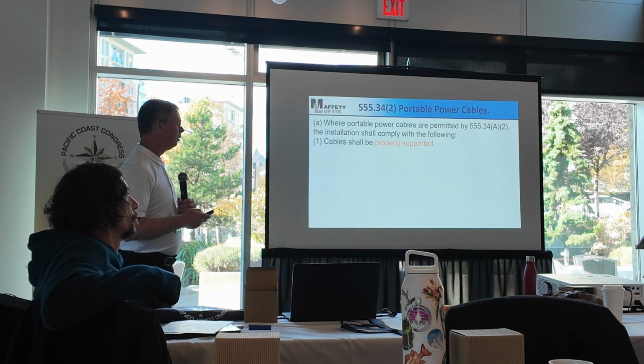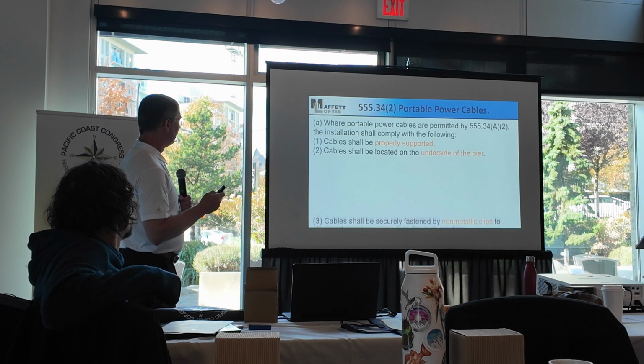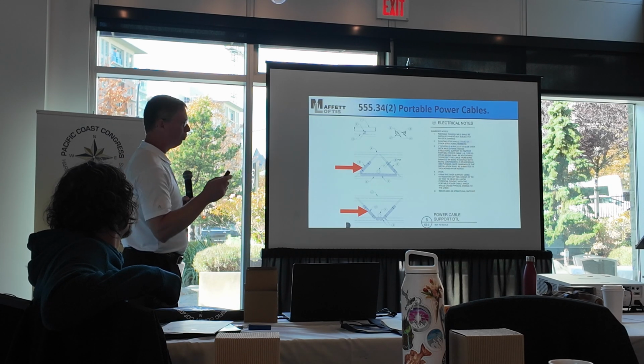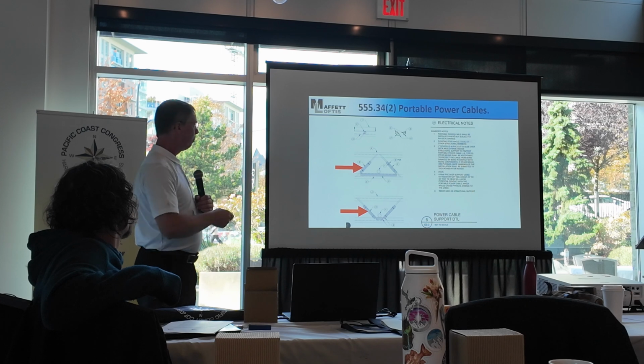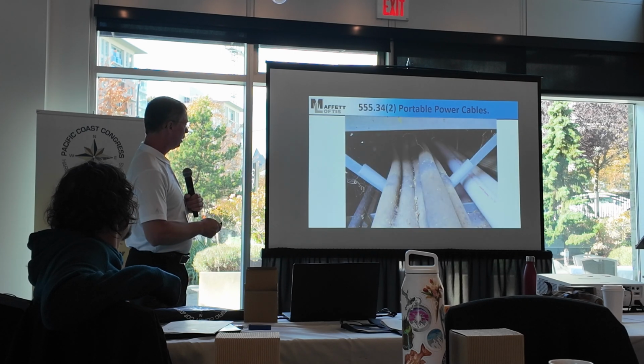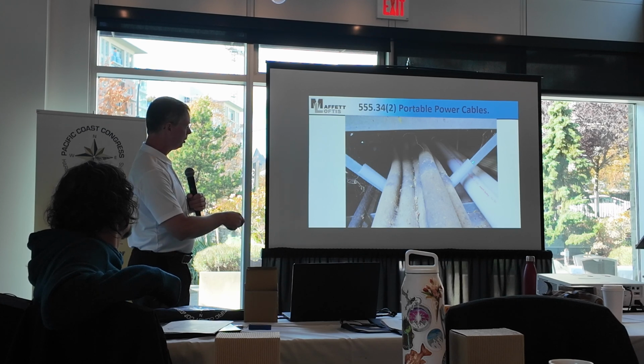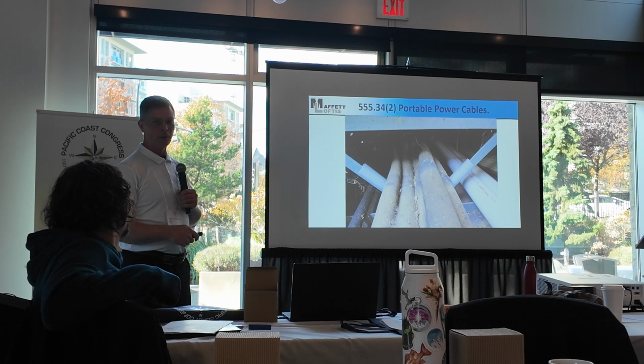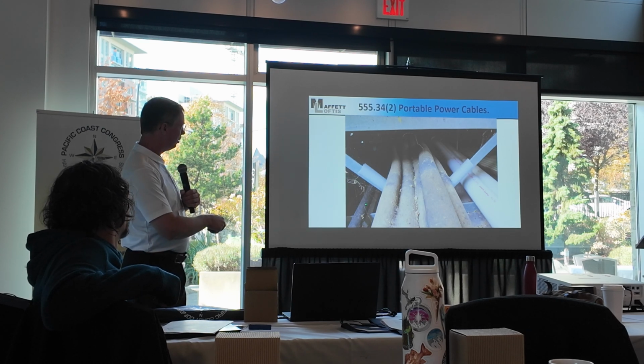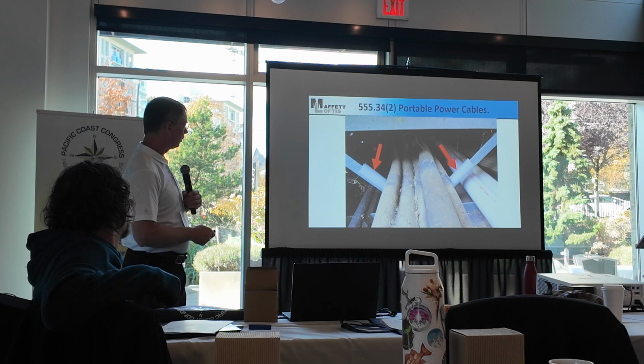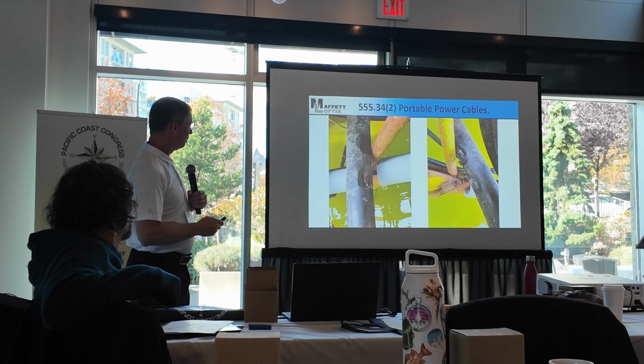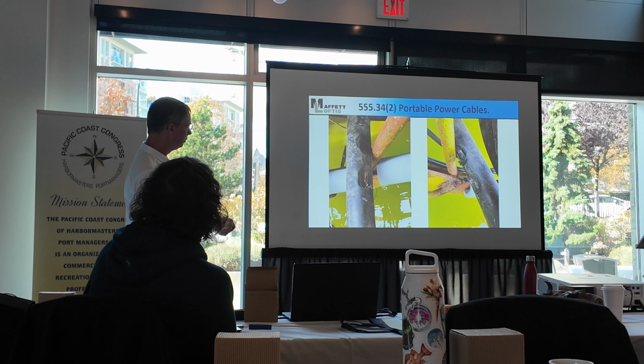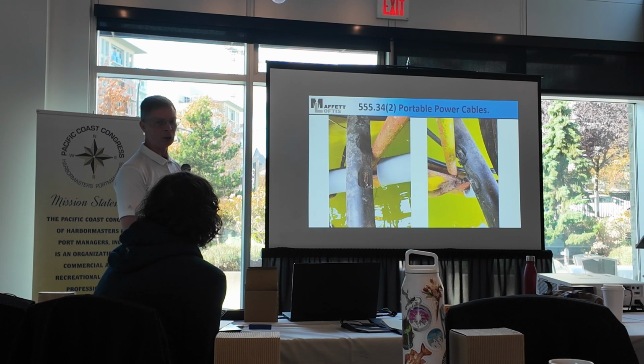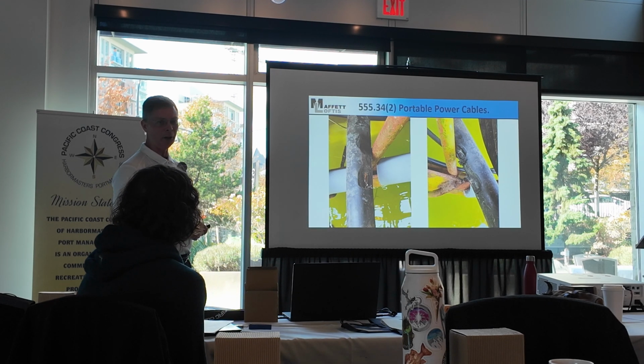Wrapping it up. Let me go through this one thing. Portable power cable. Make sure that if it's through a metal structure that we've got proper protection. This is a new boathouse. You see the PVC protected against the galvanized. The contractor ran it over here. It would have been real easy just to lay it in here and not lay it on the metal. It's close enough. And this right here, what can happen? Actually, they tried to put PVC protectors in, but they didn't do it quite well enough.